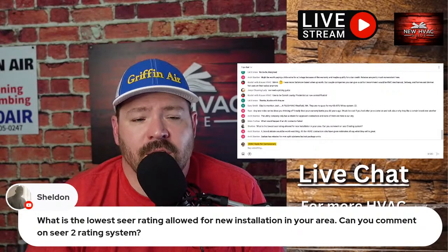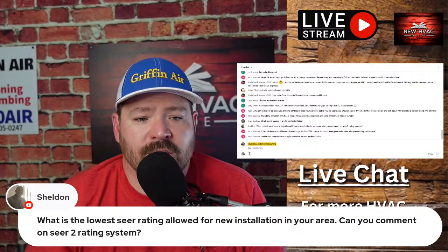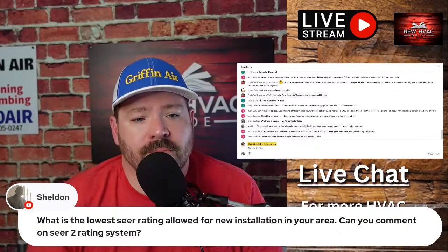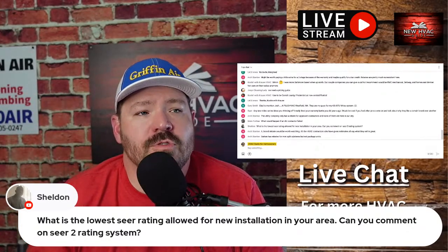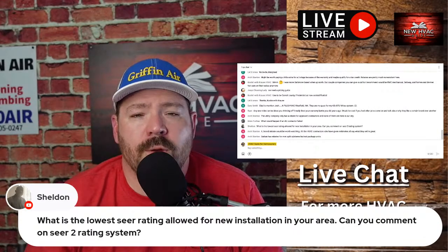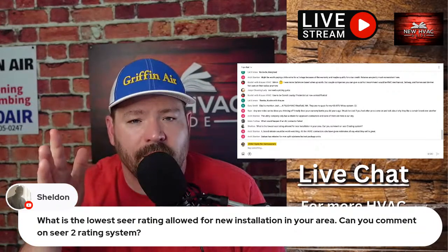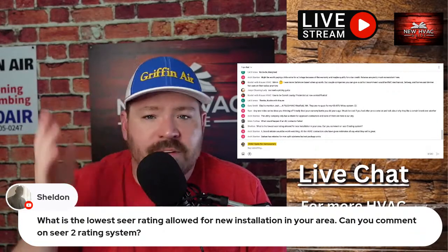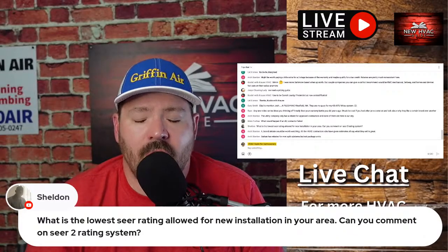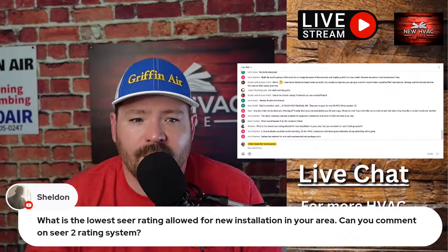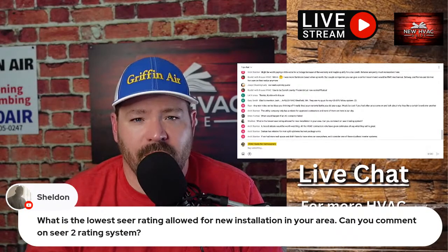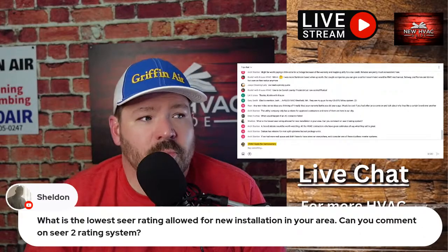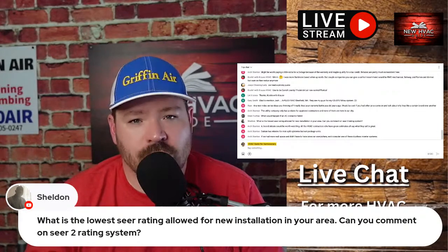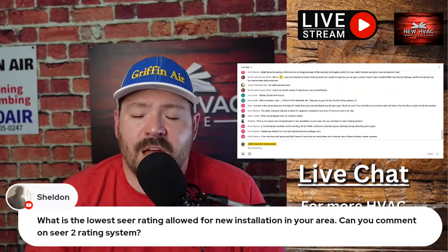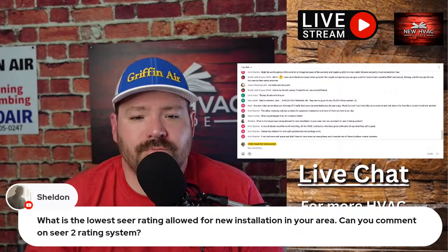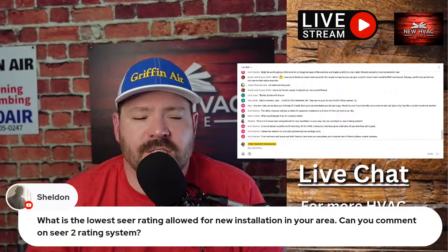I don't even think it's fair to the homeowner to use these ratings when you have, say, an inverter system, and then ask, well, what about non-communicating versus communicating? What's the SEER rating? There's a big difference there too, especially with some of these technologies, since non-communicating inverter systems can still operate very similar to how a single-stage system would. Is it an inverter system? Yes, but it's still running at 100% capacity, or very close to it, a lot of the time, because it's non-communicating. So it'll be interesting to see how that all shakes out.